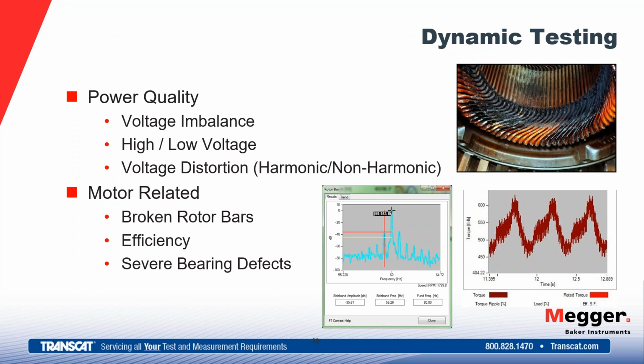Other motor-related issues. We definitely have power quality that we can look at. It's usually from the connection point of the sensing point down upstream from where you're sensing from. We can also look at motor-related issues, such as broken rotor bars. Current also has energy expending at 2 times slip, and we can watch that. If the amplitude grows, it's an indication of broken rotor bars.